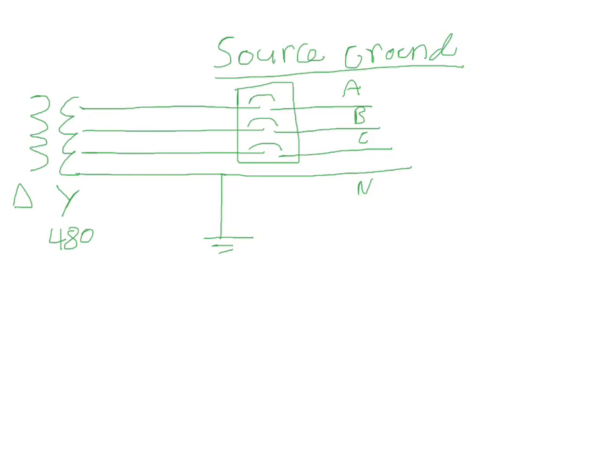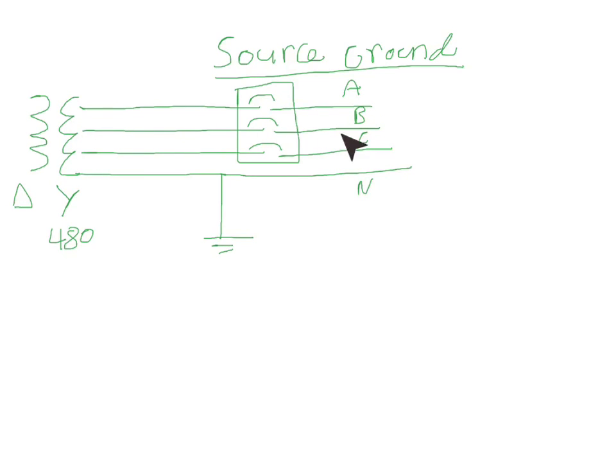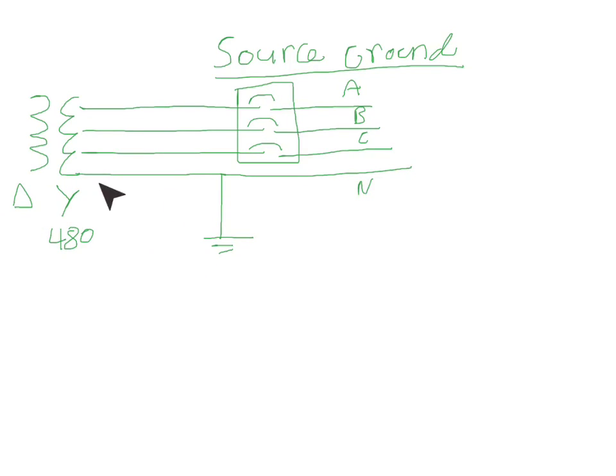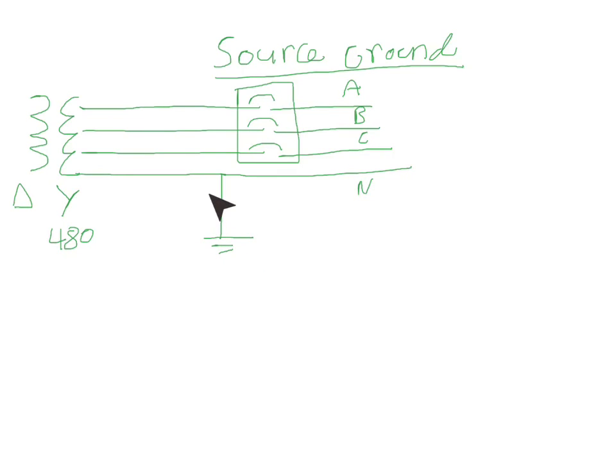Alright, so here we have our four-wire system. We have a transformer - A phase running through a circuit breaker, B phase running through a circuit breaker, and C phase running through a circuit breaker. It's a delta to Y transformer, so we got our neutral coming out. This is the neutral bonding jumper, main bonding jumper, and this is our main circuit breaker right here.